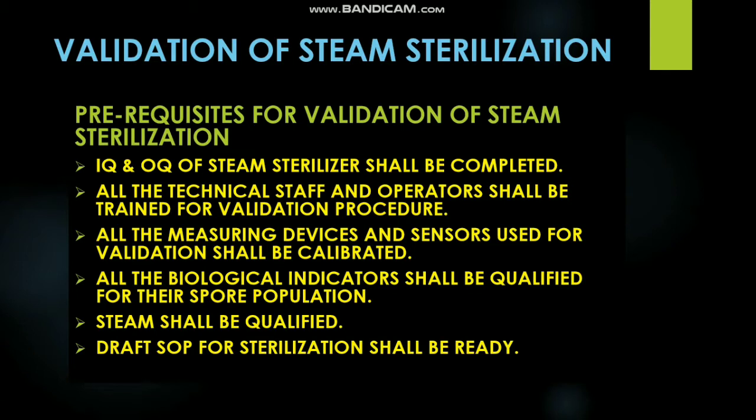Steam shall be qualified. The quality of steam which is used for steam sterilization shall be pre-qualified for its predetermined specifications. Draft SOP for sterilization shall be ready. The draft SOP for operation of the steam sterilizer shall be with us, that is, the tentative procedure which needs to be qualified in performance qualification.